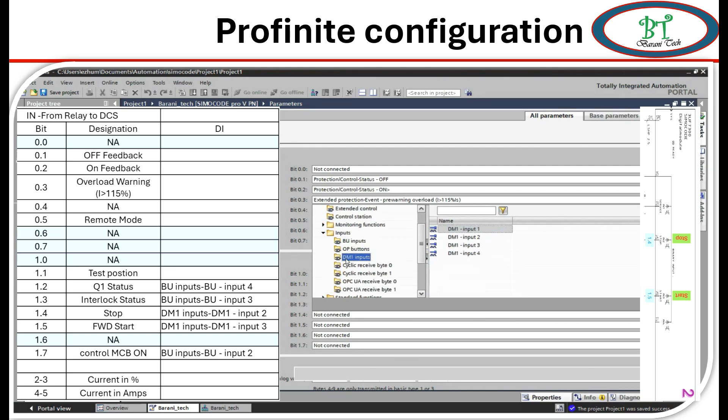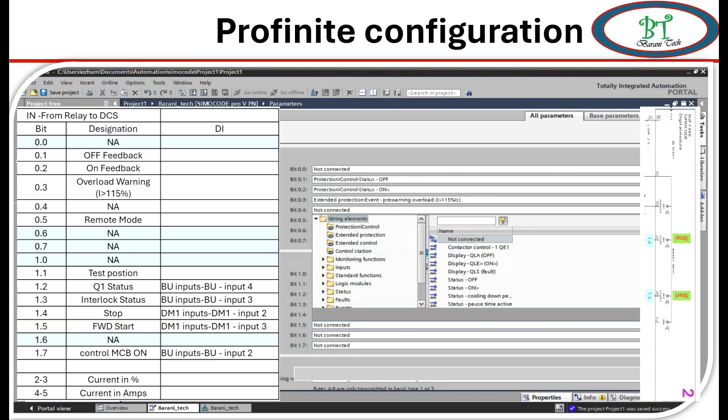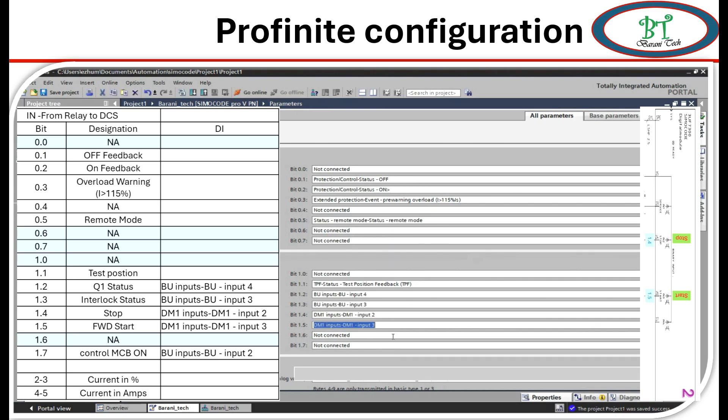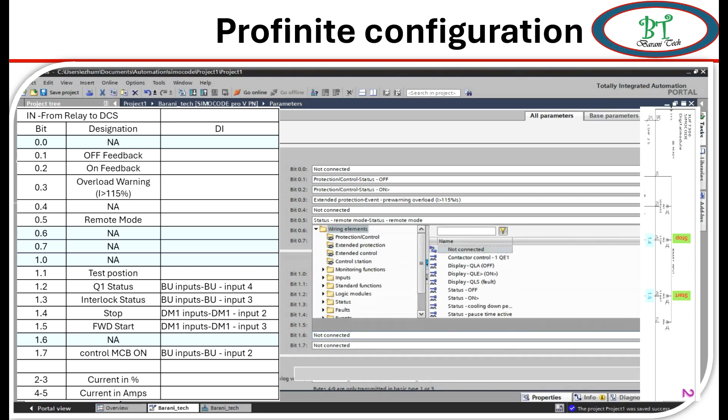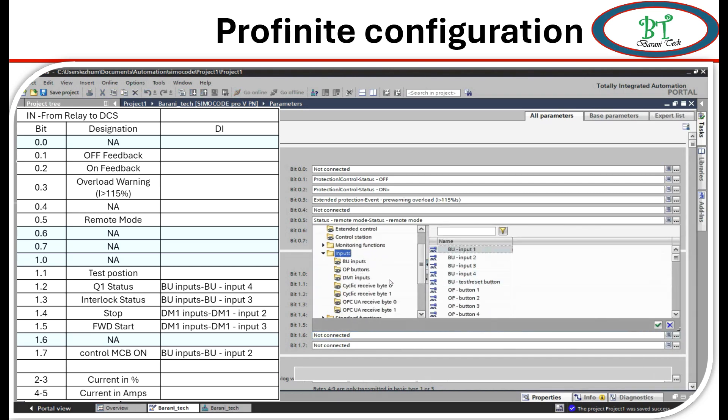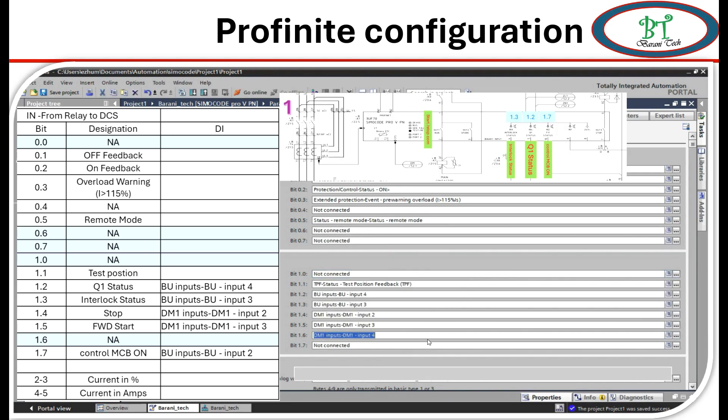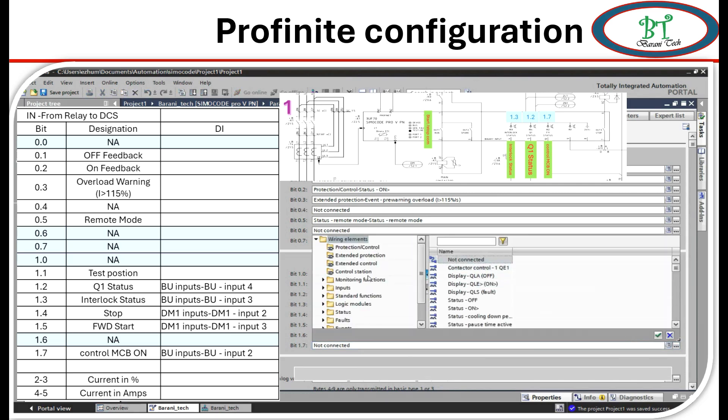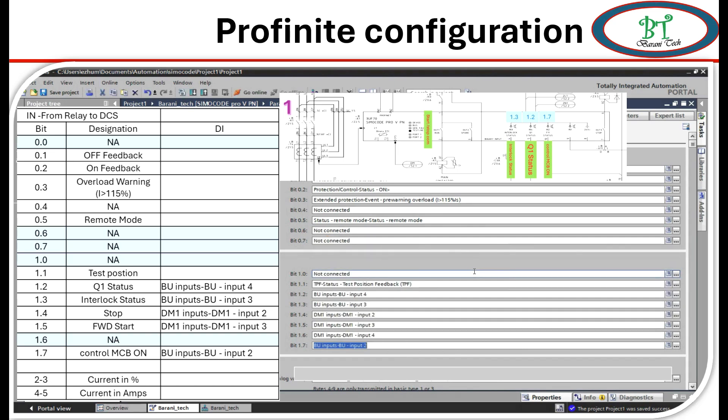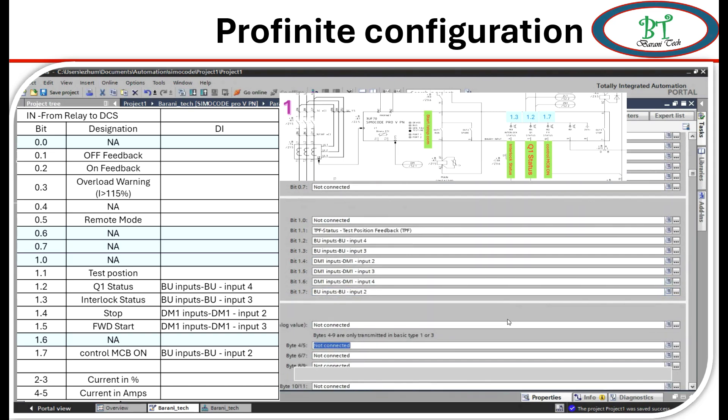And next is 1.5. It is a forward start signal or nothing but a start signal. It is also from the binary input, DM1 binary input 3. And next is input 6. And this no need to configure. As per this I configured is a DM input 4, but as per schematic it was no need to configure. And next input 1.7. It is a control MCB on signal. It is a BU input 2. Now all input signal has been configured.